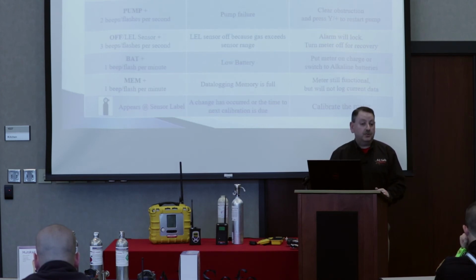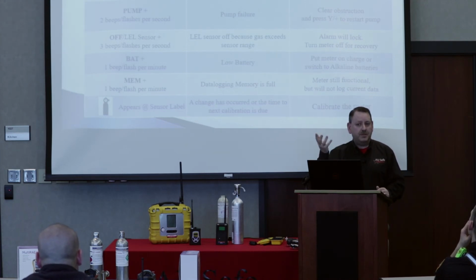So that's the next one, is your low alarm, and it will beep and flash at you 2 times per second. Once you get comfortable with this meter, you'll just be able to hear the difference between a high alarm and a low alarm. The next alarm I'll talk about is NEG.